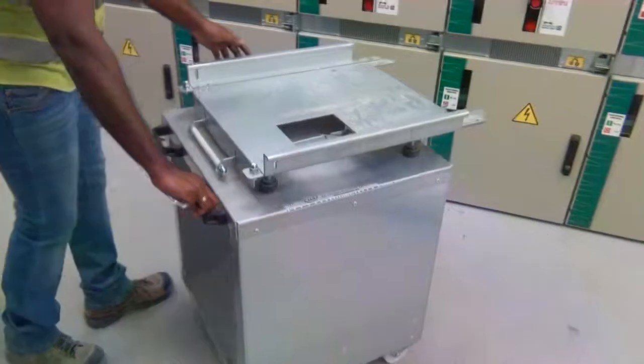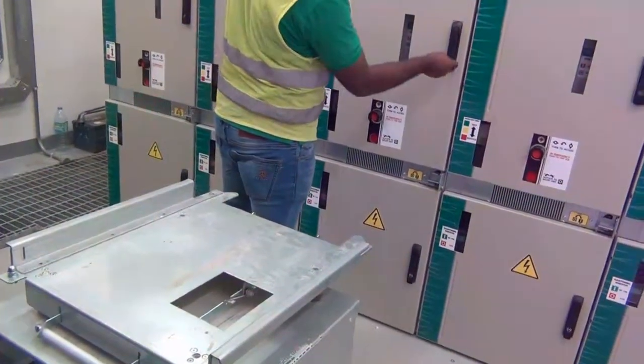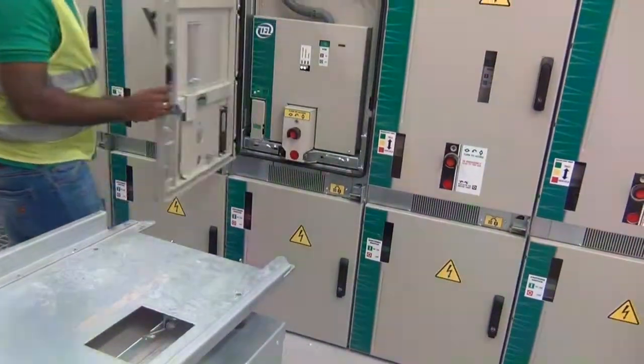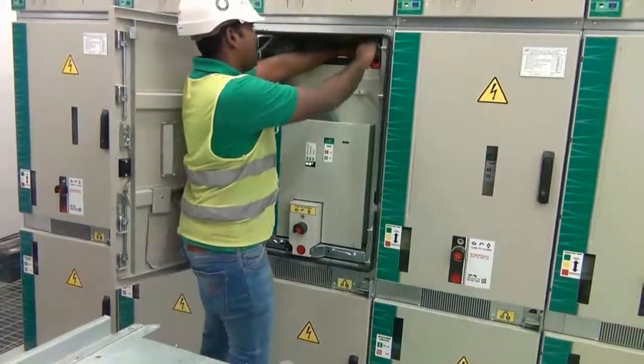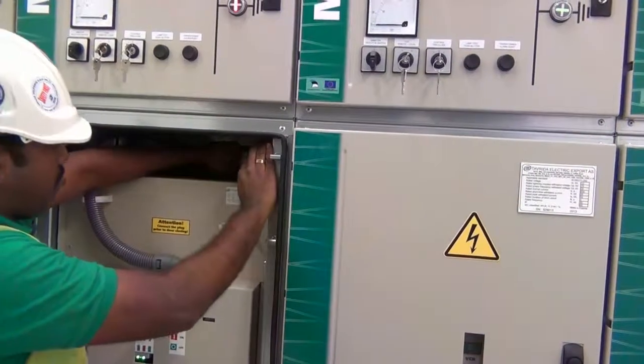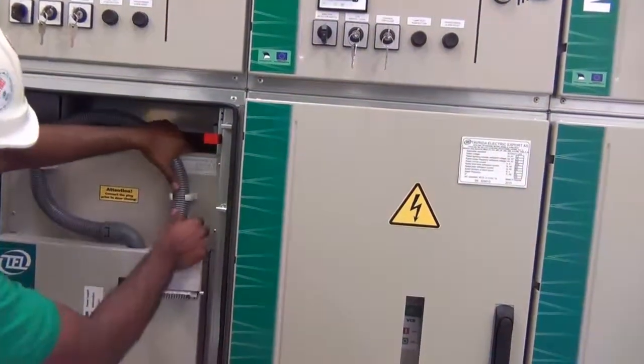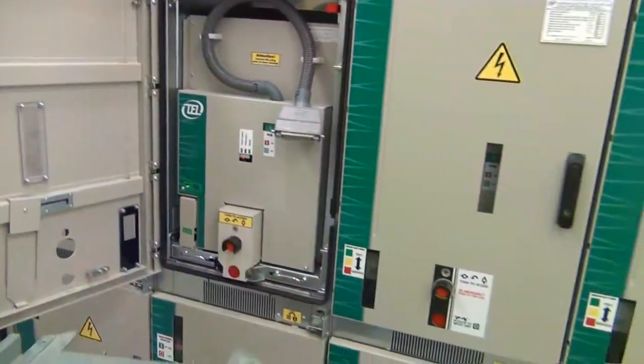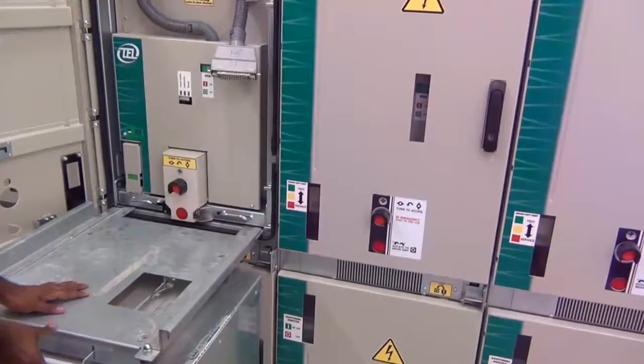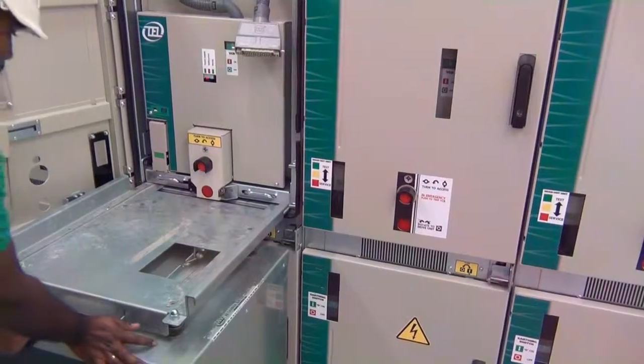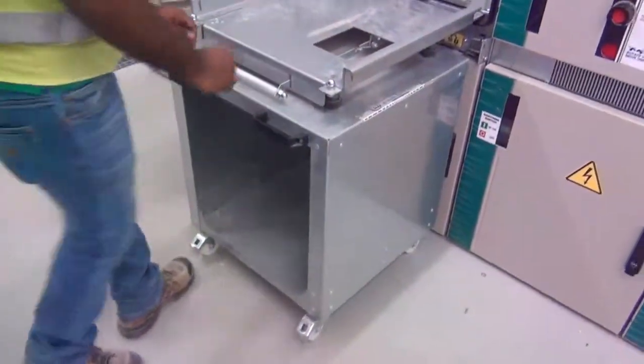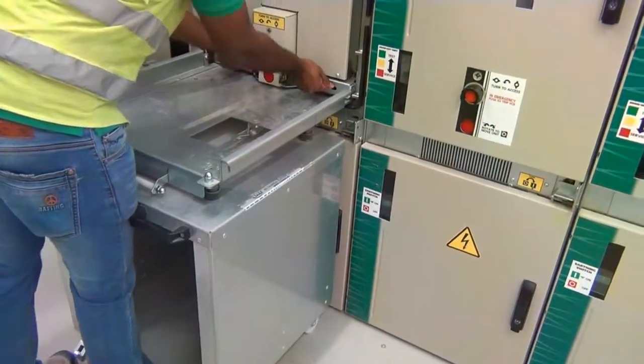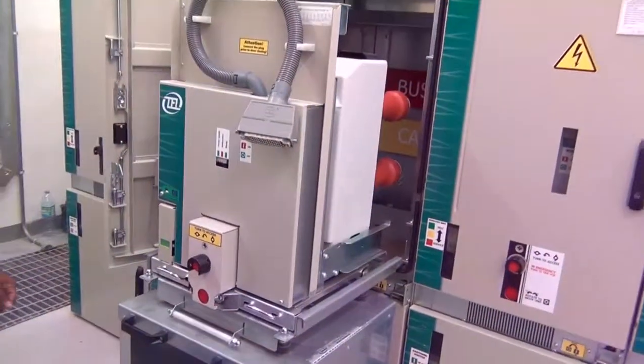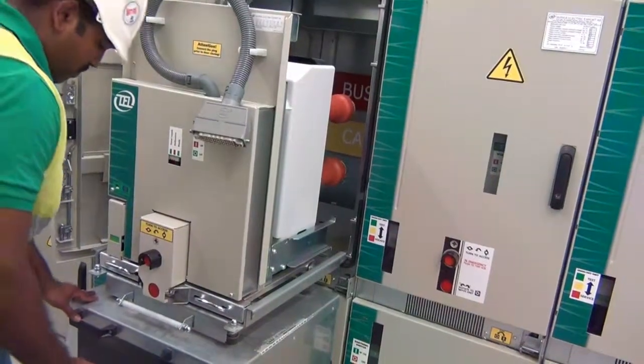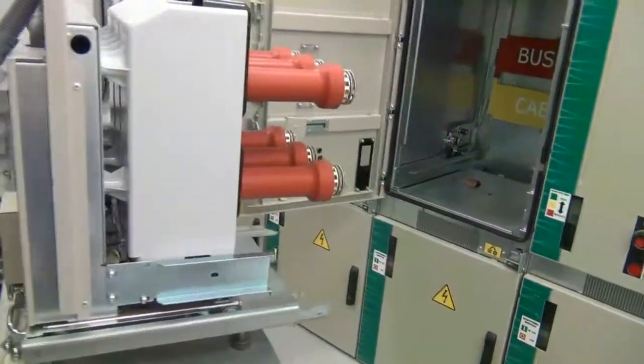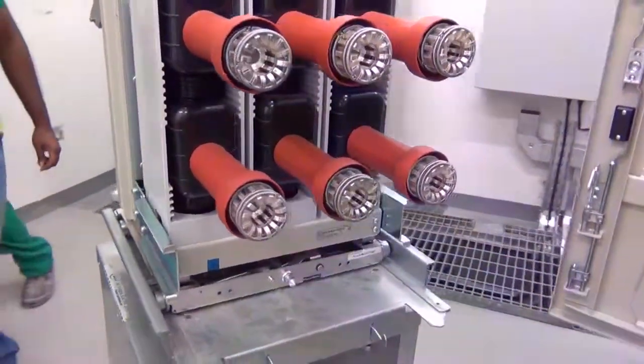Breaker trolley is given for the same purpose. Since the breaker is in test condition, you can bring it out. You have to first remove the low voltage plug. Breaker is fixed. So a single man can easily take the breaker outside, and now we can put it outside. The breaker is now completely in draw-out condition.